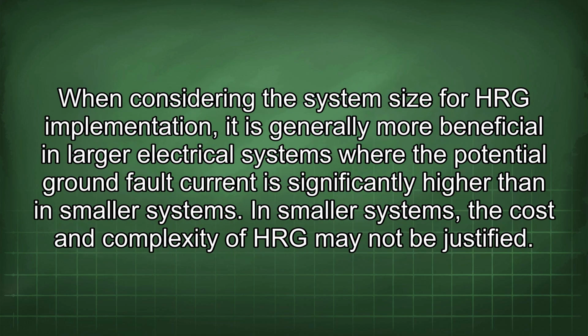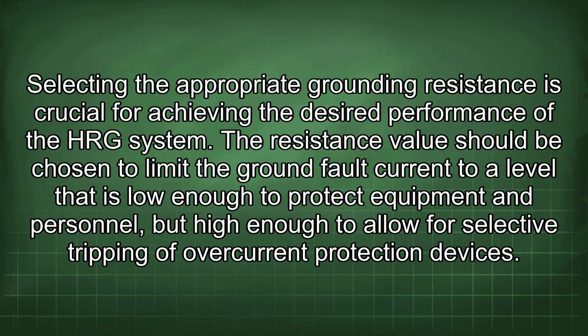When considering the system size for HRG implementation, it is generally more beneficial in larger electrical systems where the potential ground fault current is significantly higher than in smaller systems. In smaller systems, the cost and complexity of HRG may not be justified. Selecting the appropriate grounding resistance is crucial for achieving the desired performance of the HRG system. The resistance value should be chosen to limit the ground fault current to a level that is low enough to protect equipment and personnel, but high enough to allow for selective tripping of overcurrent protection devices.